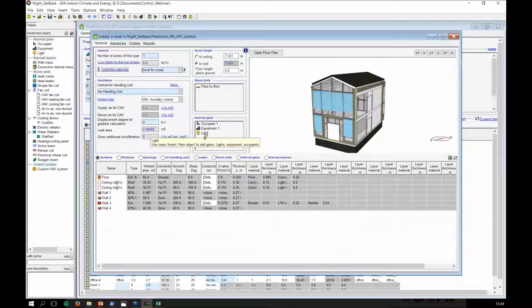Yes, well, with this VAV signal and humidity, you're able to control the ventilation signal as well as temperature in the zone. And when you place an occupant in the zone, that automatically generates humidity. You can also put in equipment that generates humidity as well. Actually, I think swimming halls are quite specific. We have a separate plug-in for that called Ice Pool and Rink, which can handle the moisture. We don't have it, we haven't purchased it yet, but I know there is a possibility. Okay, you know it's available.